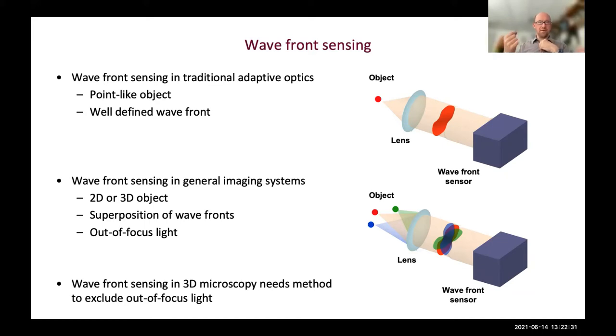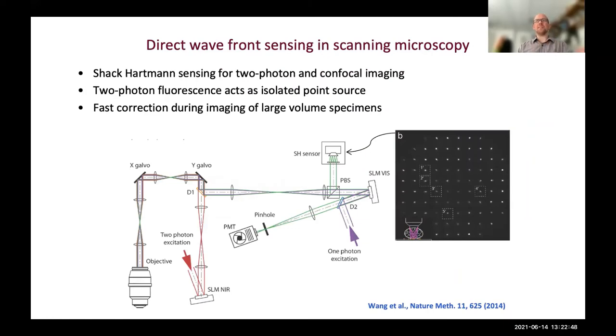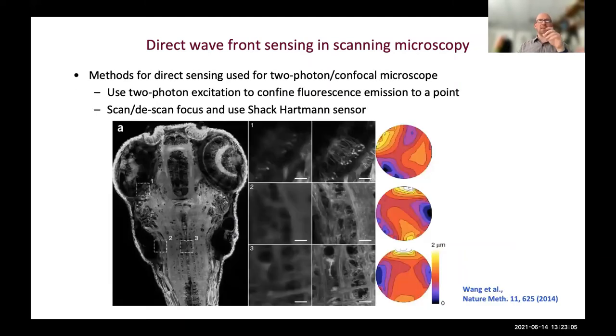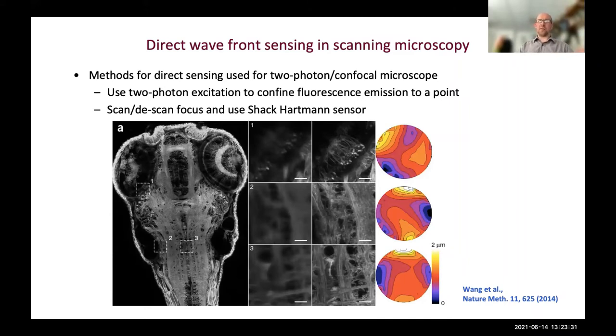One way to use wavefront sensors effectively in microscopes is with two-photon excitation, where you know fluorescence only comes from the focal spot - effectively giving you a point-like guide star, as in telescopes. The most effective implementation I know of is from Eric Betzig's group, where they use two-photon excitation to create a source for a Shack-Hartmann sensor, enabling on-the-fly correction of aberrations. Combined with deconvolution enabled by the adaptive optics, this made considerable difference in relatively thick but transparent zebrafish embryos. However, wavefront sensors are not a general solution for all types of microscopes.